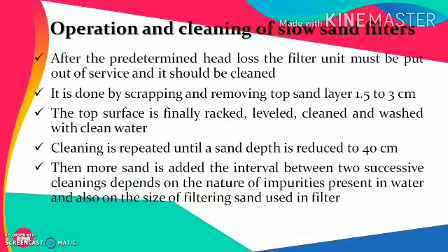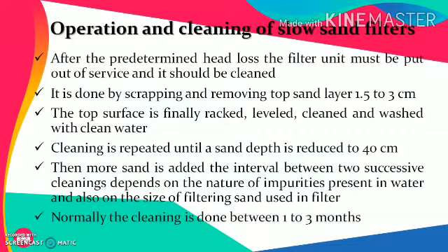The interval between two successive cleanings depends upon the nature of impurities present in the water and also on the size of the filtering sand used in the filter. Normally, slow sand filter cleaning is done between 1 to 3 months. So it should be cleaned in 1 to 3 months. Once again, it depends upon the nature of the water and the amount of dirt accumulated in the filter.